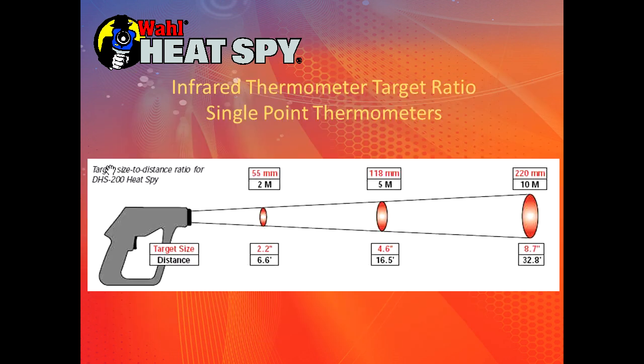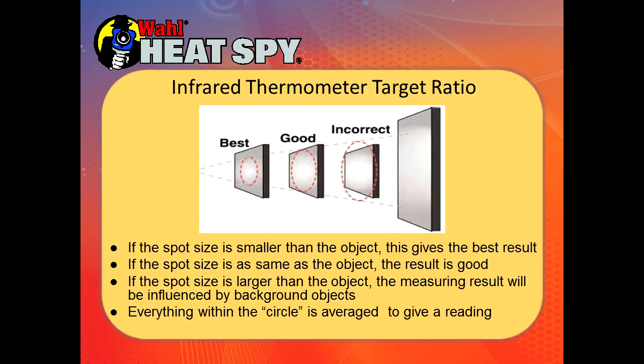If you look at a single point thermometer, the target is a circle. As you back away, like a flash dot on the wall, the target gets bigger — so the unit is measuring everything in that circle. Many people believe when you pull the trigger, a laser dot goes out and bounces back. That laser is only a pointer. The infrared energy is being picked up by the imager — it needs nothing from the laser to read the target; it's simply collecting the data. There's a parabolic mirror inside. Energy coming off the target is concentrated by the parabolic mirror onto a thermopile — a cluster of specialized thermocouples — that generates an electrical signal read as a temperature.